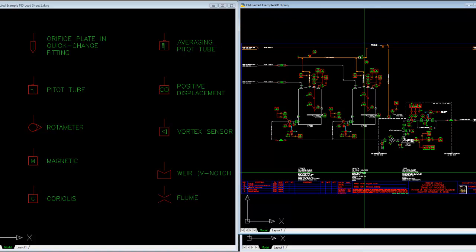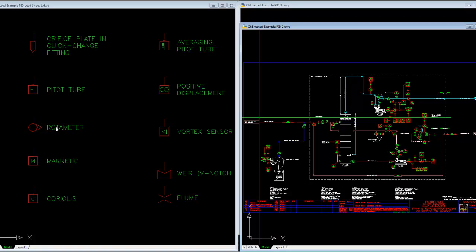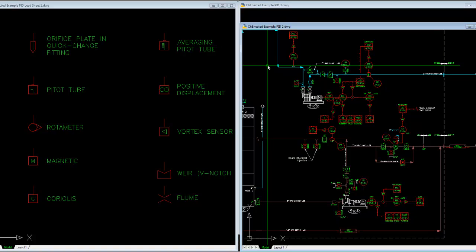So, arguably, it's not important to get hung up on the type of flow element. Although, you should be aware what it is when you see it because when you get into a process review and you're talking about operability concerns, somebody may raise the point that a particular type of device does not function well in a certain condition. An example of that may be where you have an ultrasonic device or a transit time flow meter where a lot of solids may be present in the line. Then you have a situation where the transit time will not perform well. That could lead to some improper readings and it could cascade some operability or safety concerns.